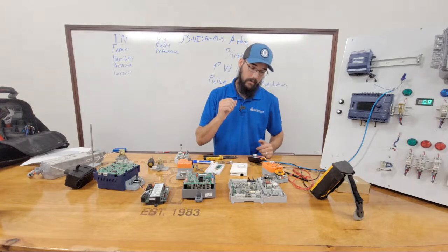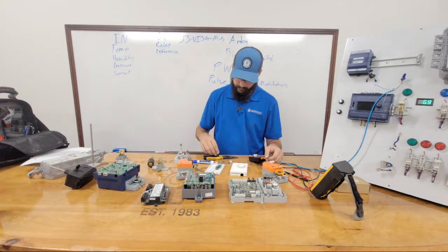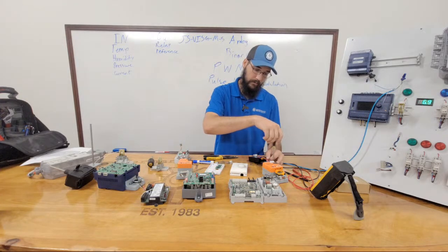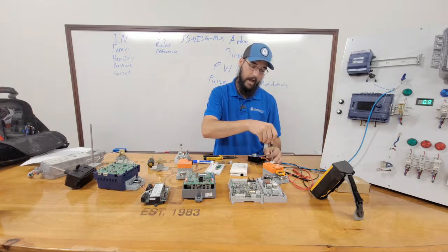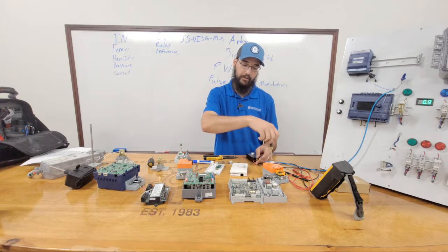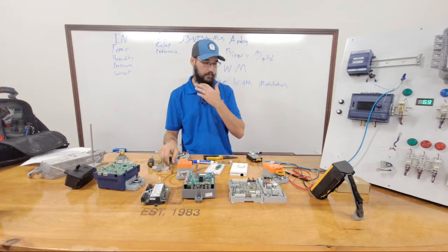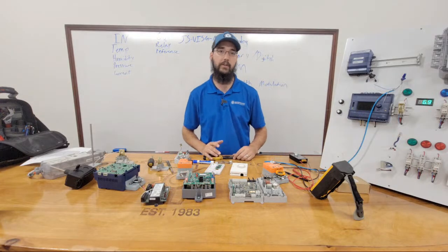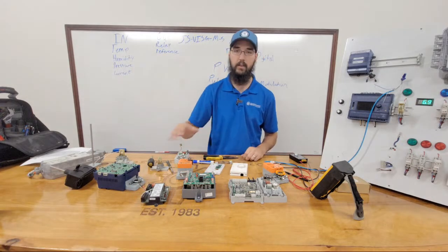So in a perfect world, if you did not have the signal generator, then my suggestion would be to go find an actuator or find something else and do the actuator first, right? So these actuators are a few $100, right? Plus some of your time to change them, okay? A lot less cost than this.